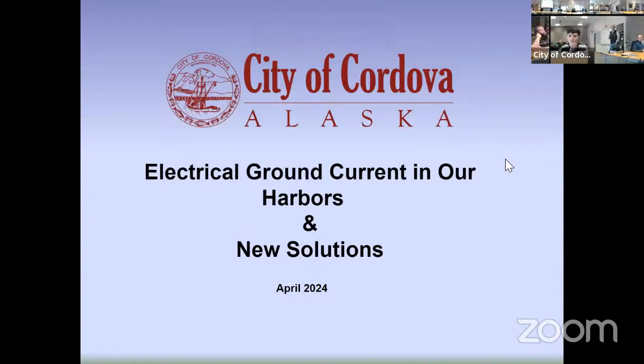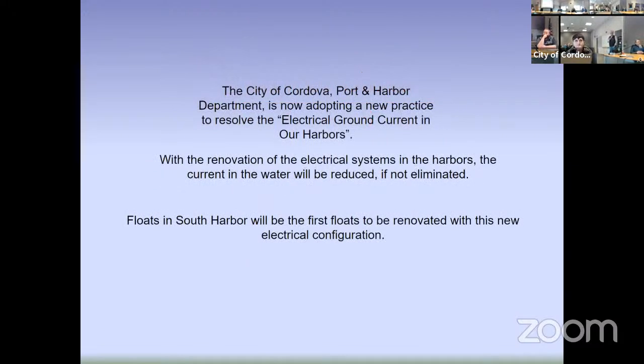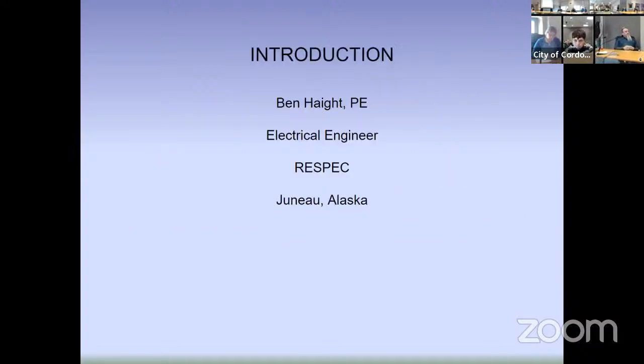I have a slideshow presentation, and what our primary interest is, is the electrical systems in the harbor, the new electrical systems that now include protection for ground current, or sometimes we call it stray current. So with code revisions over the past few years, we are now required to install circuit protection that will trip the circuit breakers when ground currents exceed certain amounts. That's what we're going to talk about. With the renovation of this harbor, we're including that. This has been going on for a number of years now. It's finally caught up to us here in Cordova.